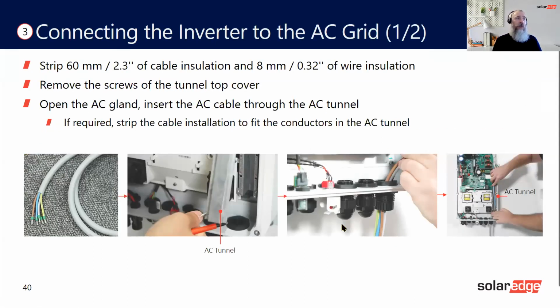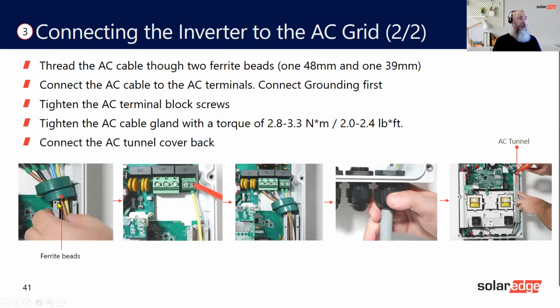What we're doing on here is we're removing the AC tunnel. This is just a compartment that houses the AC connection. So the AC cable comes in the bottom, as you can see up here, and then runs up the top, and the AC connects in here. So same place on all the inverters. It connects in exactly the same place. All we're doing is just using this tunnel to protect it, to keep it separate. As you can see, there's the cable in the tunnel in here. Also, we've got some ferrite beads that you must put around the cable as well, and then secure the tunnel back on. So the AC cable now goes through, has the ferrite beads at the top, and that's it. That's the AC done, pretty simple.